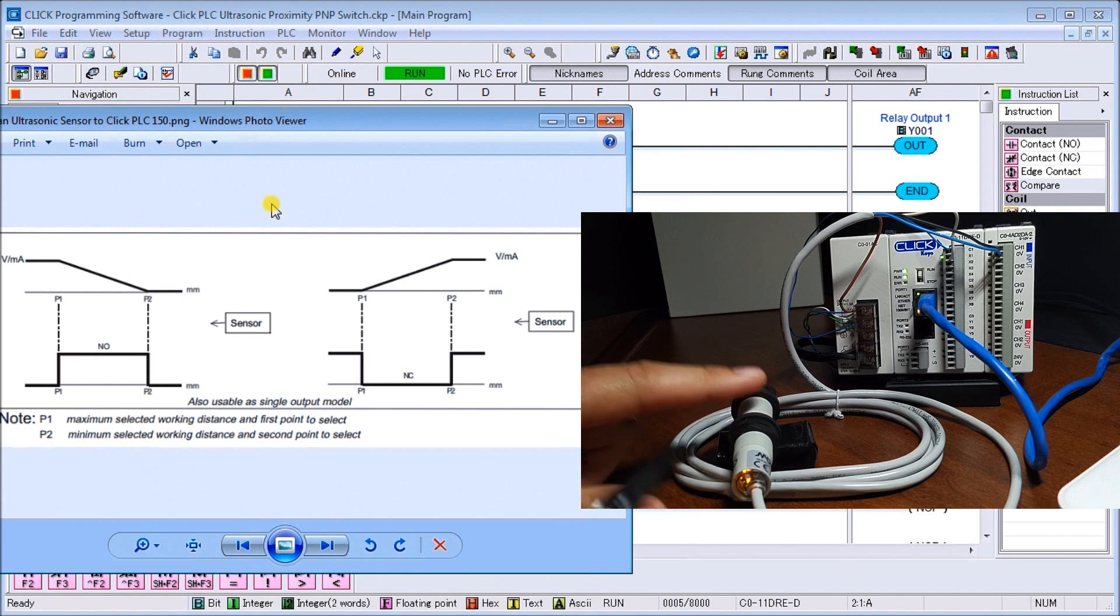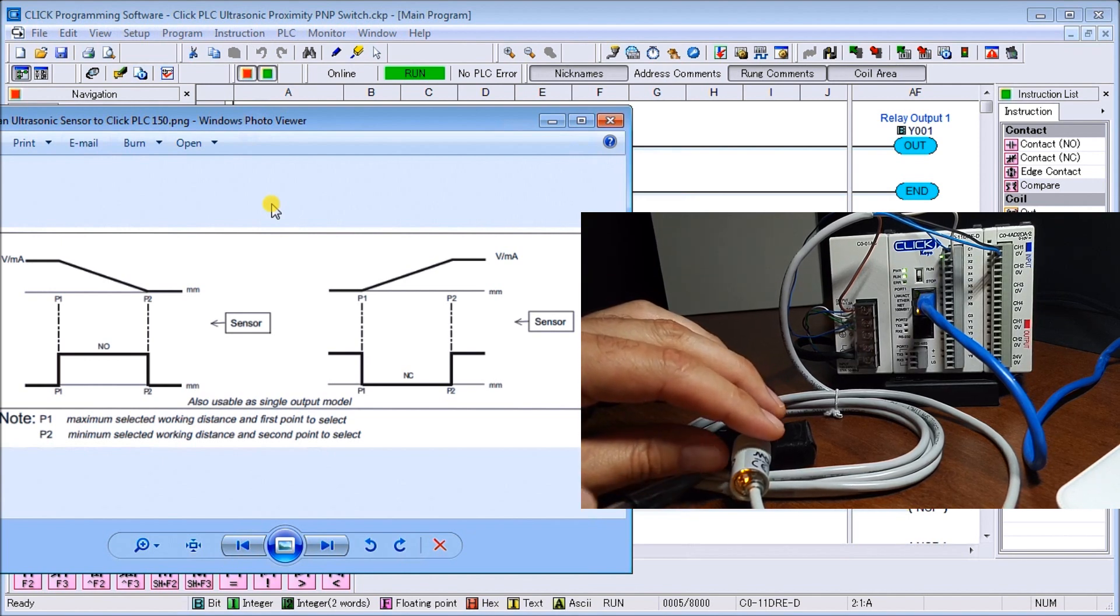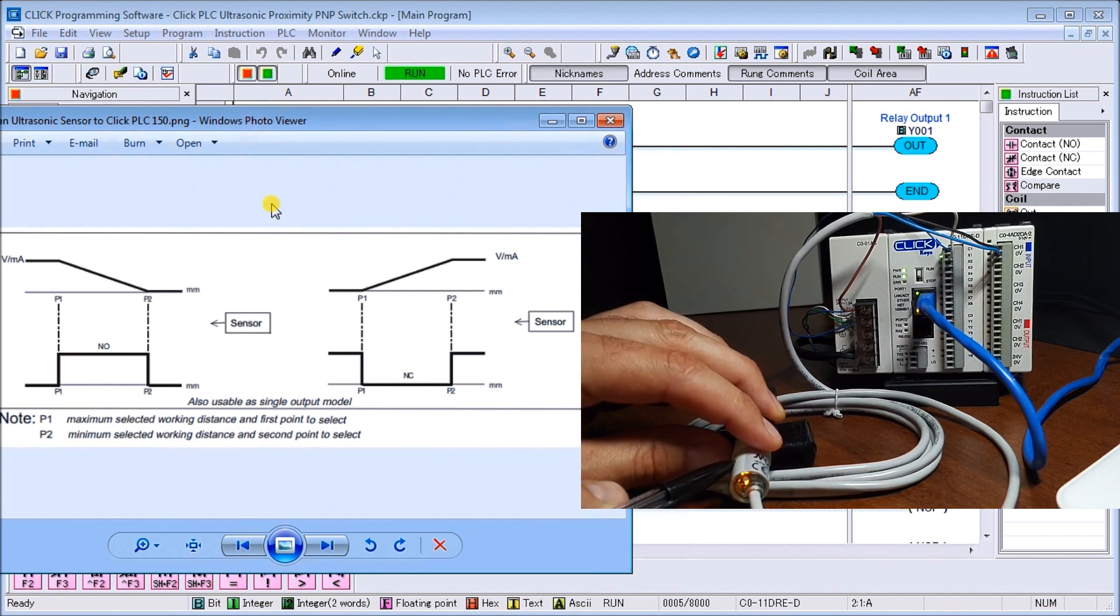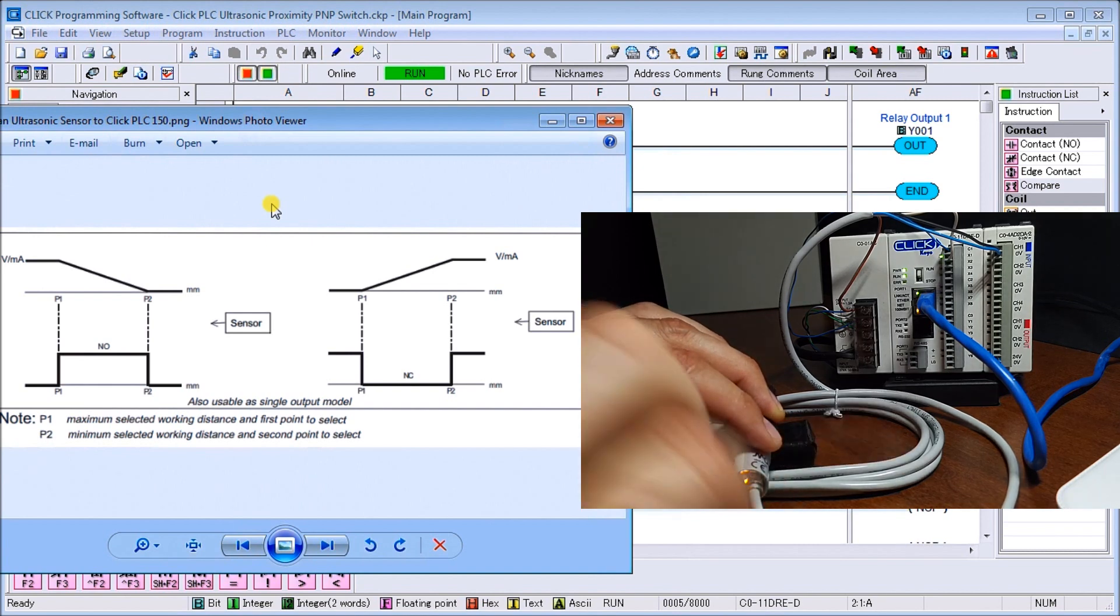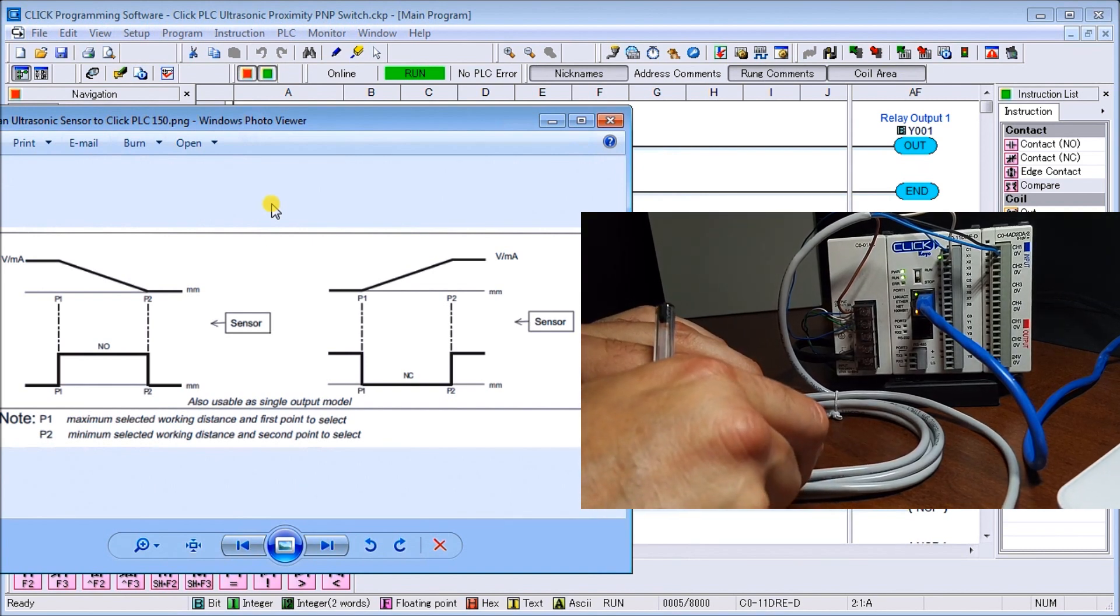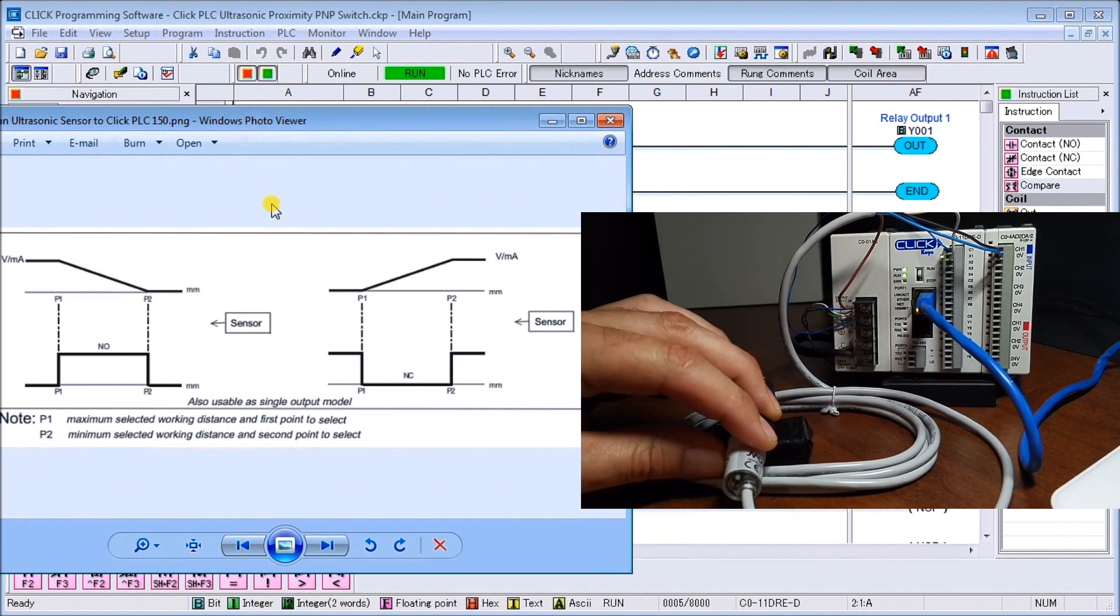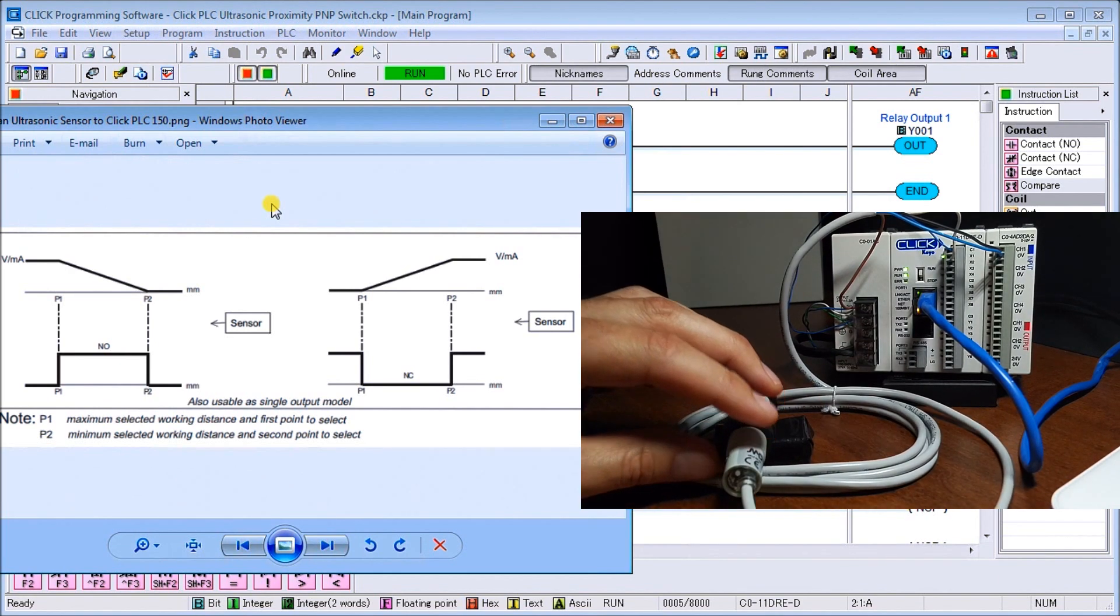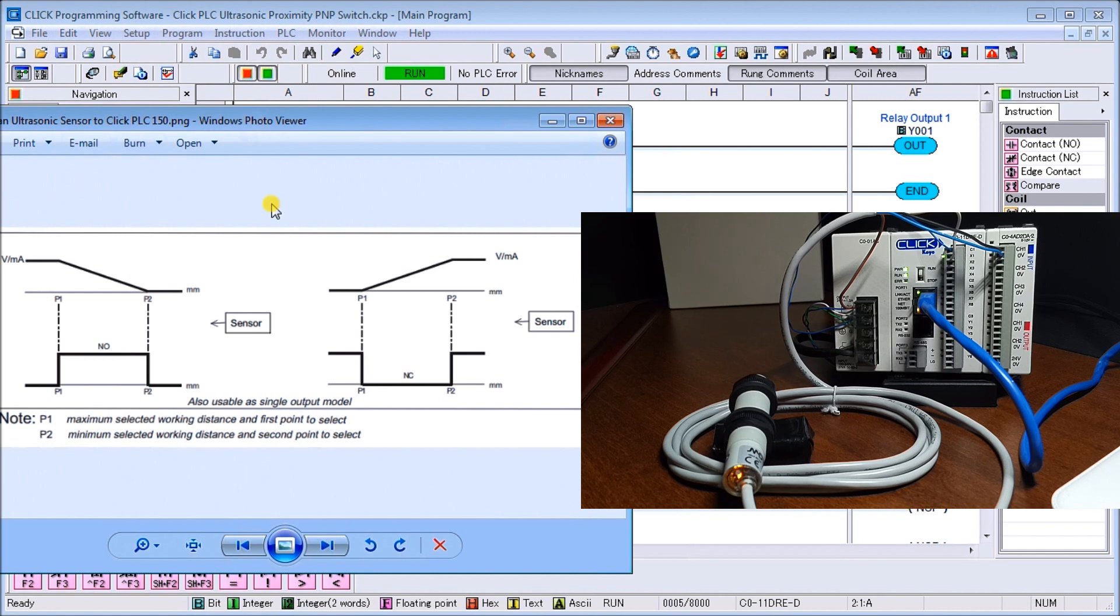I hit and hold that switch with a target present. I'll move my target here, we'll leave it about there, and we can say okay that's going to be my 20 milliamp. So I'll hit the button and hold it for a second, and then it will come on, off, and then on again, and now it's set for my 20 milliamps.